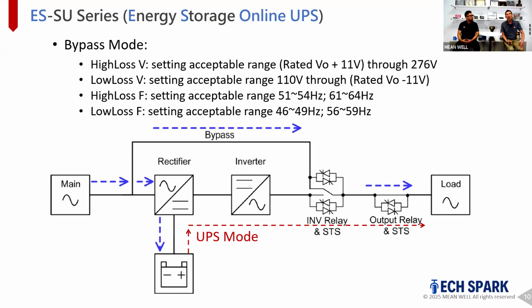Sure, I'm gonna go over here. So high loss and low loss means it allows the user to set the window voltage of the AC input where it goes out of bypass mode. For example, if your nominal input is 208, you can set the low loss to like 190 and high loss to 230. If the AC power line fluctuates down to 180 or above 240, it's going to skip bypass mode, stop it, and go to inverting mode. So it's really suitable for applications where the user wants to set the window to not bypass.